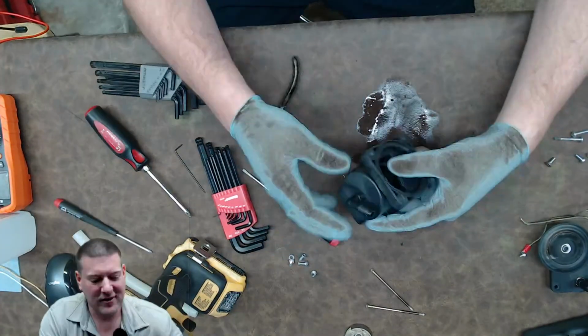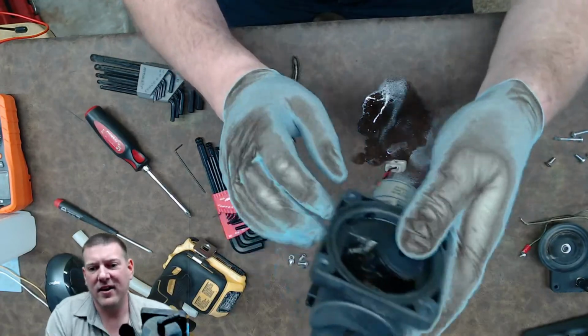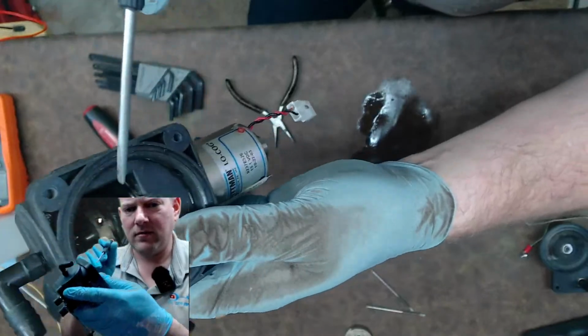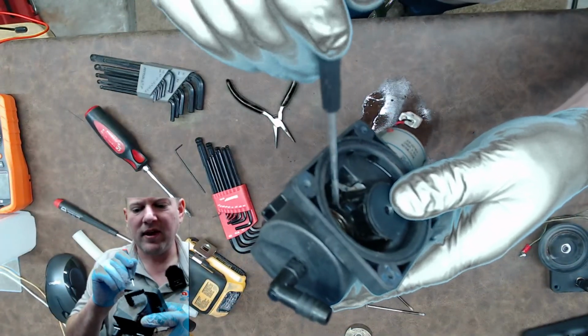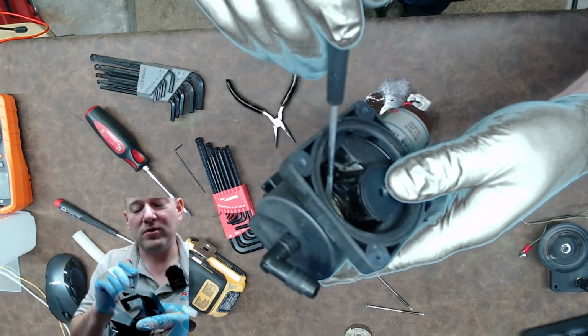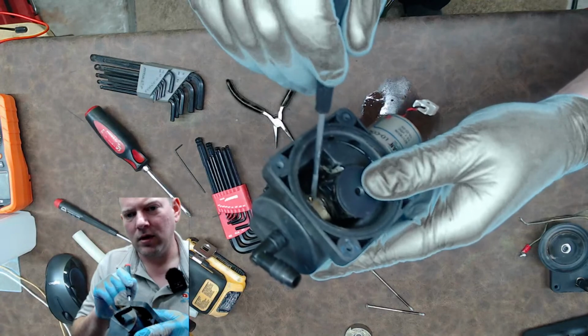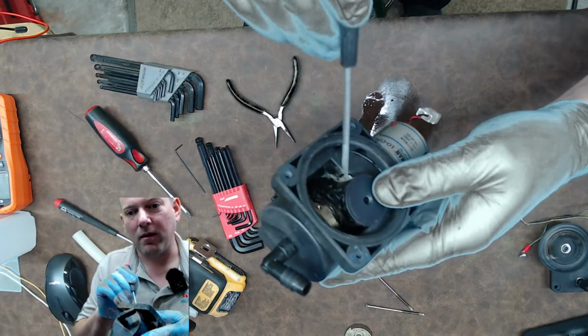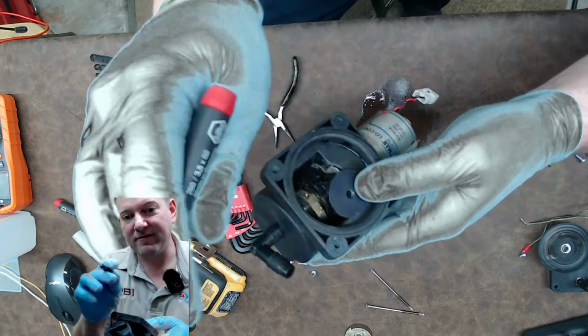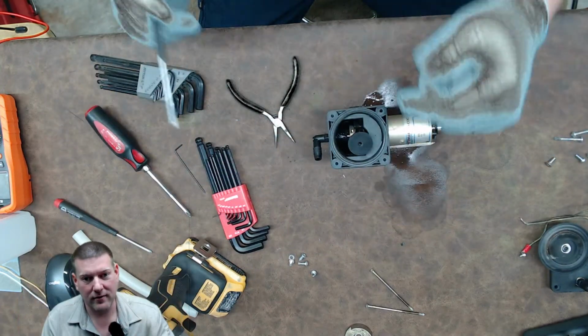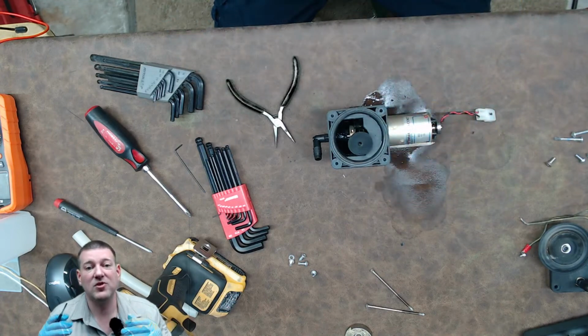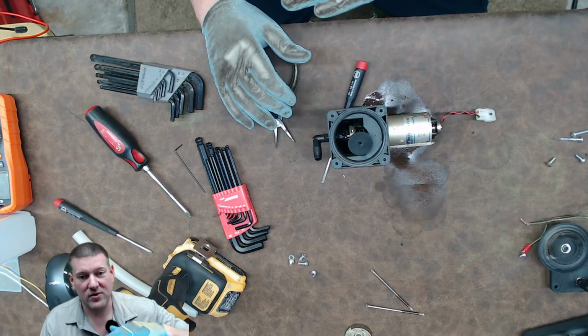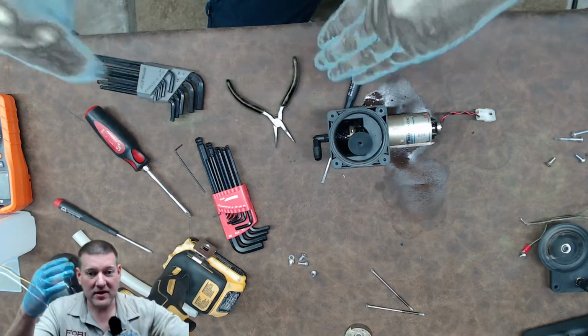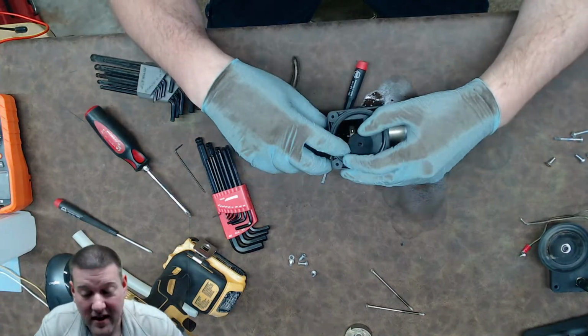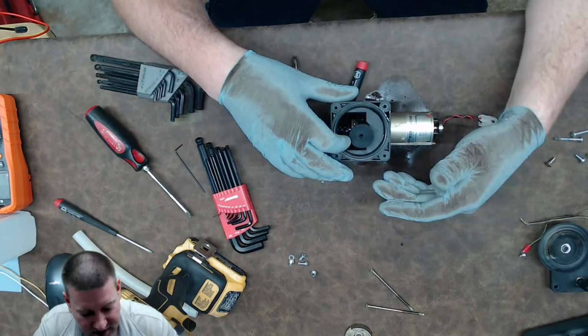Anyway, at the very least, this pump is absolutely wasted. So there's a sealed bearing. Hold on, there we go. There's a sealed bearing right here. So you have a counterweight, which is basically the flywheel, and then you have a sealed bearing inside the crank arm. That sealed bearing has the shaft of the motor going completely through it. So the shaft of the motor is connected to the eccentric weight, or the flywheel, and what it's supposed to do is offset the force of the diaphragm. So as the crank arm goes up, the weight goes down. They're doing this constantly and it weeble wobbles. But that sealed bearing got a bunch of schmoo inside it and is absolutely seized.